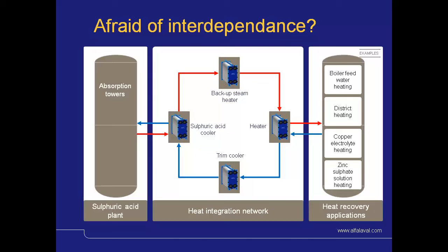In this kind of connected systems, people may be afraid of interdependence. Well, if the sulfuric acid plant stops, there is a backup steam heater installed, so the heat can be supplied anyway. And if the nearby plant shuts down, there is a trim cooler installed, so that the heat from the sulfuric acid plant can be cooled off anyway. All these backup units are accounted for in the study that Alfa Laval has made.